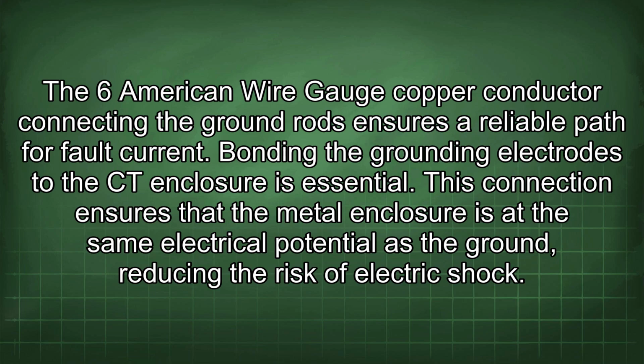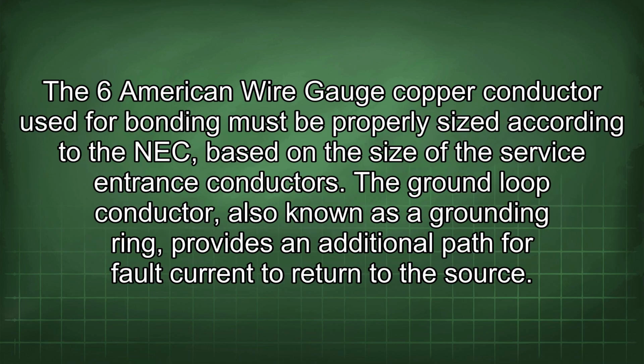Bonding the grounding electrodes to the CT enclosure is essential. This connection ensures that the metal enclosure is at the same electrical potential as the ground, reducing the risk of electric shock. The 6 American wire gauge copper conductor used for bonding must be properly sized according to the NEC, based on the size of the service entrance conductors.